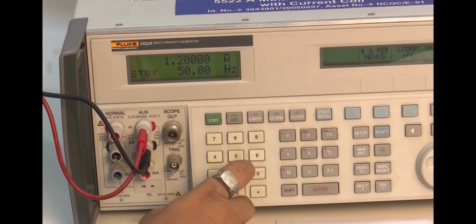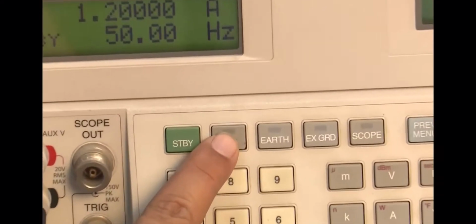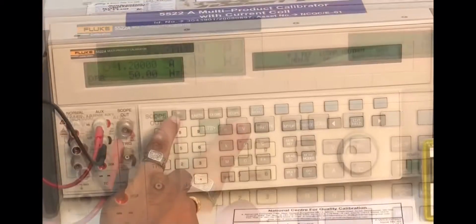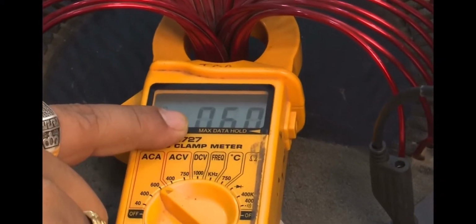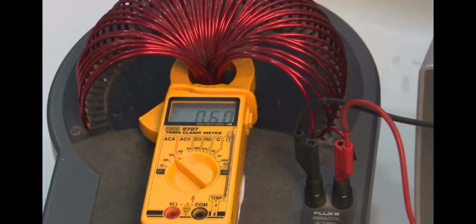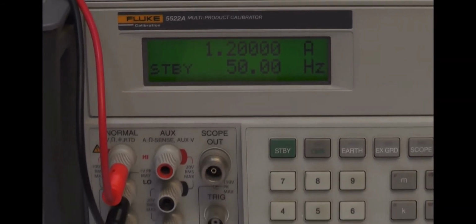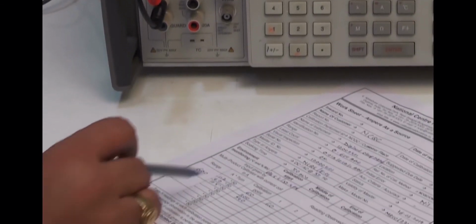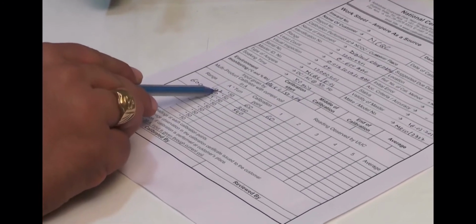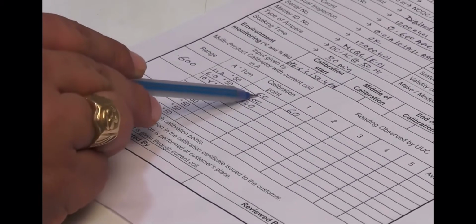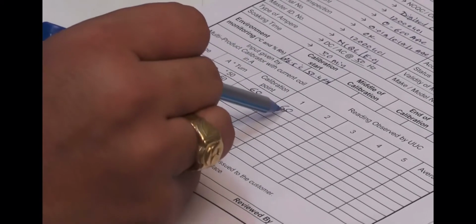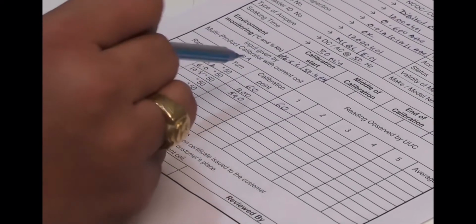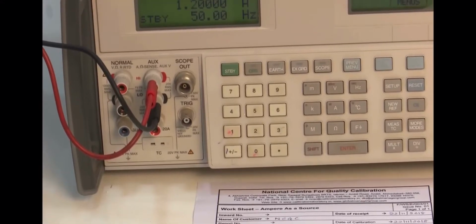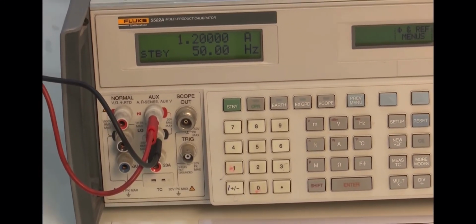Now I am pressing OPR, meaning the operate button, of the multi-product calibrator. When I press the operate button, the clamp meter is activated and it is displaying reading 60 ampere against 60 ampere calibration point at 50 Hz. This is because current coil has 50 turns. So 1.2 ampere into 50 will give us 60 ampere. I am noting this reading in worksheet. This is first calibration point. Then I am pressing standby button to stop output of multi-product calibrator.